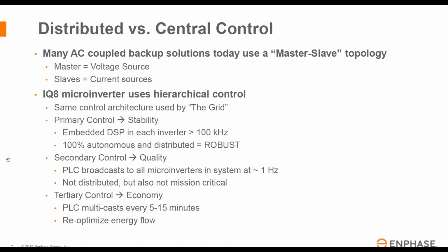We've gone to a different approach, hierarchical control, which is exactly the same architecture used by the grid today. We have 3 levels of control. Primary control governs the voltage and frequency stability of the system, and that's embedded in a DSP, a digital signal processor, in each inverter, running at over 100 kilohertz. So it's very fast and very capable. Each individual device can operate 100% autonomously, and it's also distributed, and that leads to a very robust system. The secondary control determines, I would say, power quality, and that is controlled by an external controller, which we manufacture, and that uses power line carrier communication.